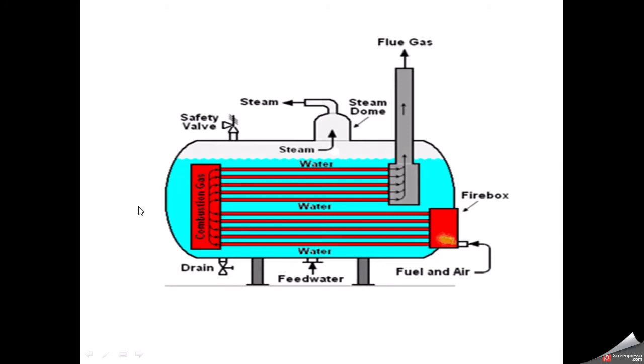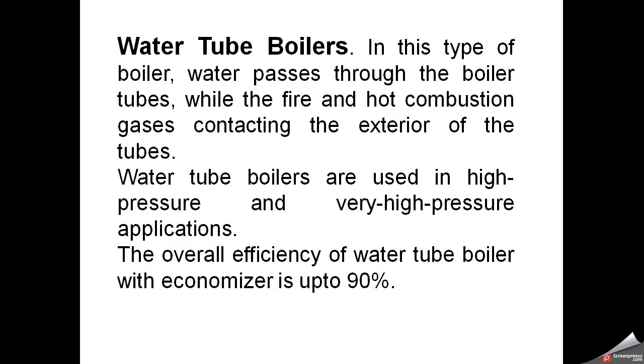The other type based on design is water tube boiler. In this type, water passes through the boiler tubes while fire and hot combustion gases contacting the exterior of the tubes. Water tube boilers are used in high pressure and very high pressure applications. The overall efficiency with economizer is up to 90%.